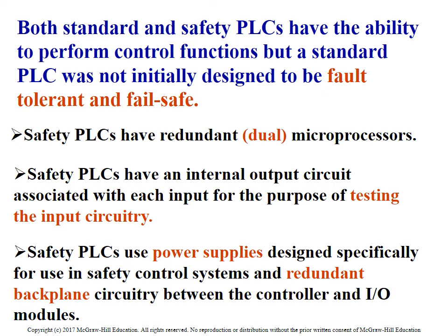So they do have the ability to perform control functions, but a standard PLC is not initially designed to be fault tolerant and fail safe. That's what we mentioned before. Just make sure that you're aware that they're very easily manipulated and their design is not fail safe, whereas a safety PLC has redundant microprocessors that are double checking themselves all the time, making them more fail safe.